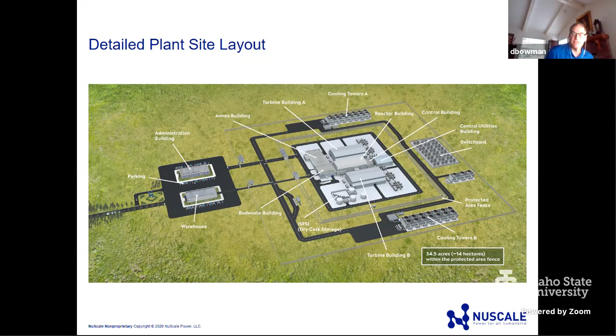Now, UAMPS, the company building at INL, has requested we consider dry cooling for the main condenser and service water, which will change the design substantially. We'd have to move large dry condensers inside the fence, and they'd take up a large area because air cooling requires much larger equipment. The cooling towers would go away, replaced by condensers and a different cooling system for the service water. Air cooling is a unique technology I don't have experience with, so we're currently investigating it with some design studies.